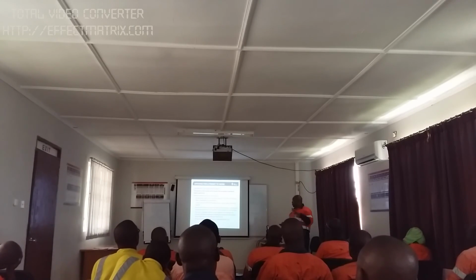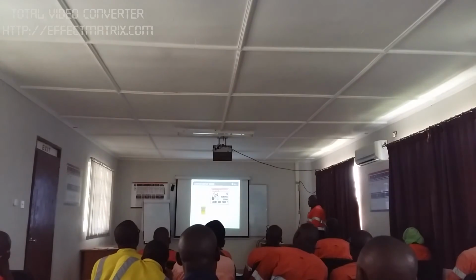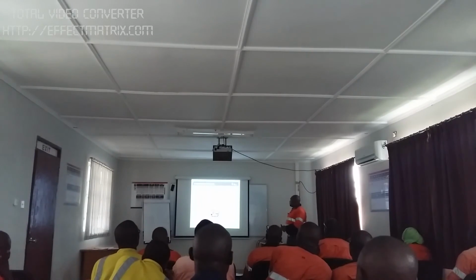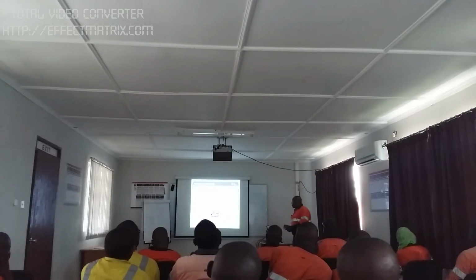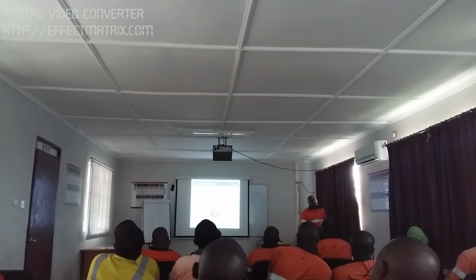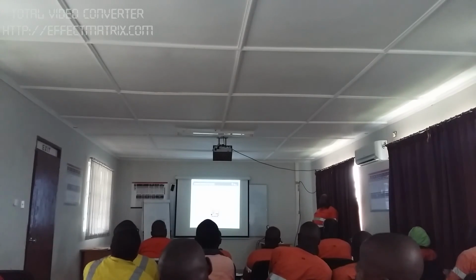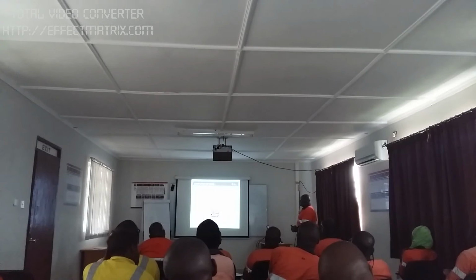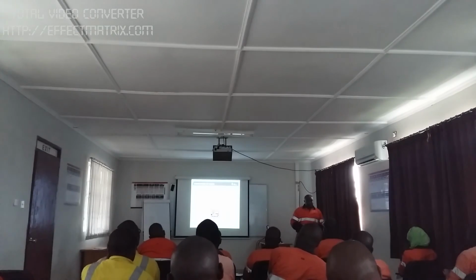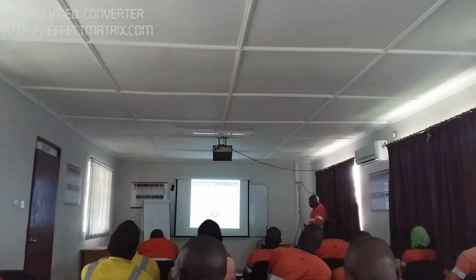The only copy that we take to the field is the blue copy, and the JSA, so that it can be reviewed from that point. On completion of work, we are required to ensure that the equipment is safe to start, either safe or redundant. So we either tag it out or we make sure that housekeeping has been done, safety guarding has been put in place, and tools and equipment have been removed and kept where they're supposed to be. Requester and workers then sign off the master isolation permits and the permit to work.